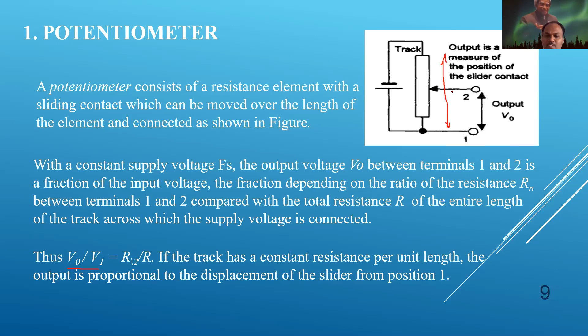Now, the same principle can be applied for rotary movement. This is linear movement, so linear displacement I can calculate with the help of a linear potentiometer. But if I want to calculate displacement in a rotary direction, I use the same principle with a rotary coil and a pointer. The same potentiometer has been converted into a rotary one, and you get a voltage output that denotes the displacement of the pointer in the rotary direction. Formulas are there that we can use for calculating output voltage. It consists of a coil of wire wrapped around a circular track, similar to the first linear displacement potentiometer. The smallest change in displacement gives rise to a change in output, which will help you calculate the angle theta. Okay.